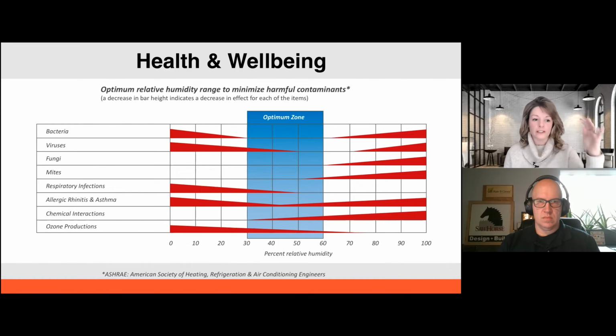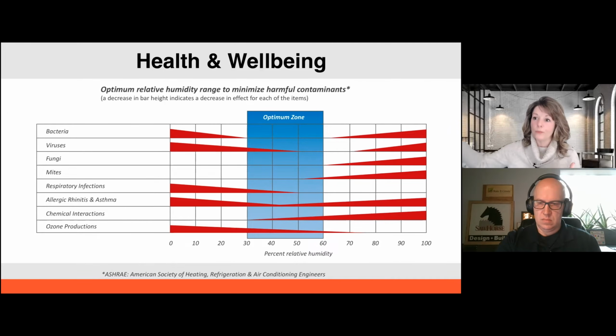But if you look on the left here, these are all the health things. And I'm going to go down to mites, because that's dust mites really. 80% of the people who have indoor allergies are allergic to dust mites. And as soon as you get that relative humidity to 50%, they die. So it's really important that in the bedrooms, in all areas of the homes where there is carpet and mattresses, anywhere where dust mites can live, we control that relative humidity to 50% or below, because then dust mites don't live. But with all these things, relative humidity is very important. Ventilation is important, filtration is important, but we have to make sure that we understand how relative humidity works.